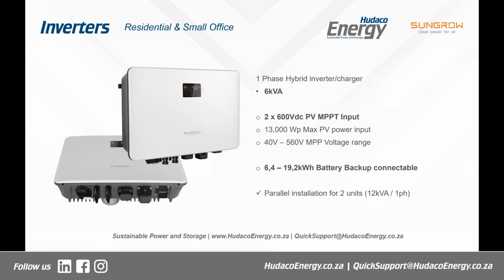This unit is part of the new Hero range. These are the hybrid inverters. It's a 6 kVA single phase hybrid inverter, two 600 volt DC MPPT inputs built in, and a massive 13 kilowatt peak power input that you can put into this unit. That's absolutely fantastic. This unit can be installed with anywhere from 6.4 to about 19.2, let's call it 20 kilowatt hours of battery backup connectable. I'll talk a little bit more about the batteries in a moment for you, the high voltage lithium ion batteries.